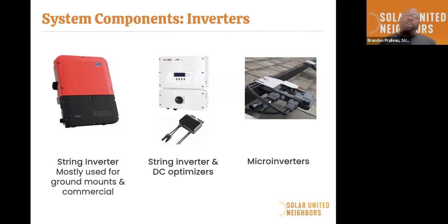Your string inverter is mostly used for ground mounts or commercial systems. On the market now, we typically see more string inverters with DC optimizers or micro inverters. The good thing about those is they allow you to calculate panel-level performance without bringing down production of the rest of the system. So if one panel is poorly performing, the DC optimizers and micro inverters will isolate that panel so it doesn't bring down the rest of the system's production.